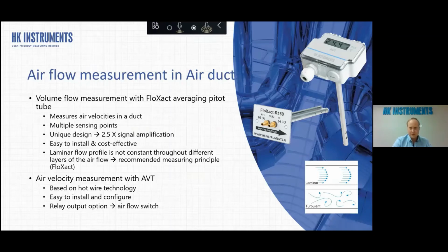So it's based on the pitot tube principle that you just connect the pressure transmitter for the high side and the low side, and the result will be the dynamic pressure, which there is a formula that corresponds to the airflow. The other way to do this in-duct airflow or velocity measurement is our air velocity transmitter AVT, and that is based on the hot wire technology. It's very easy to install and configure, and you can have it also with this adjustable relay output. So then you can use it as an airflow switch.